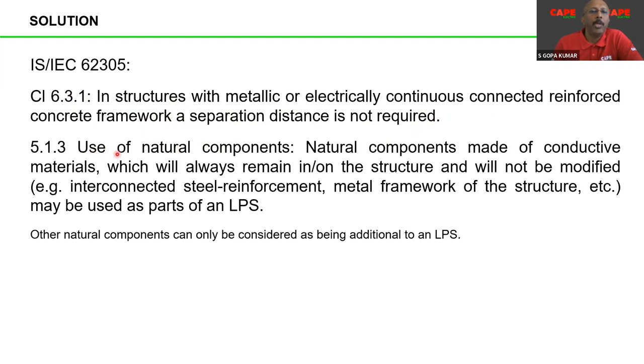For that, what you should do? Use of natural component. What is natural component? Natural component is made of conductive material which will always remain in or on the structure and will not be modified. That means the material which is used for construction of your building, such as interconnected steel reinforcement, metal framework of structures, etc., may be used as part of lightning protection system. That means the reinforcement and metal framework. So other natural components can only be considered as being additional to LPS.